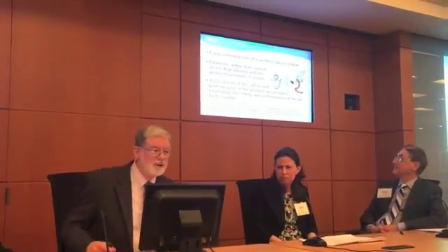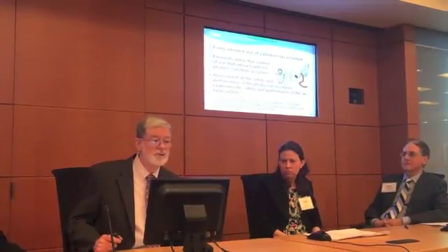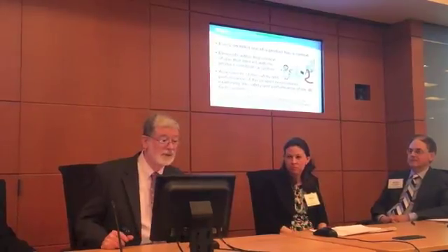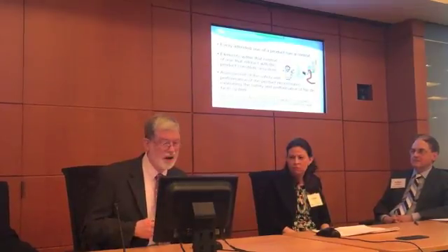These days, more and more devices have connectors or wireless connections that exchange data with other devices. And what are the implications of that for safety? Let's look at that. Every intended use of a product has a context. Elements within that context of use that interact with the product constitute a system. And that's starting to sound a whole lot like that definition that I showed you in the first slide, right? A system is just a set of interacting or interrelated elements. So it's this de facto system that's defined by your intended use that's the system that you have to think about the safety of.